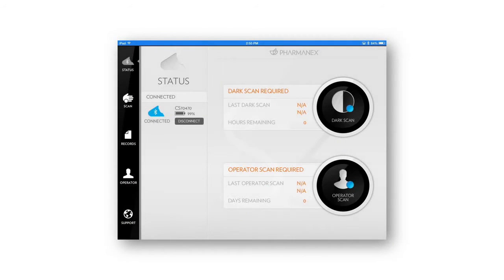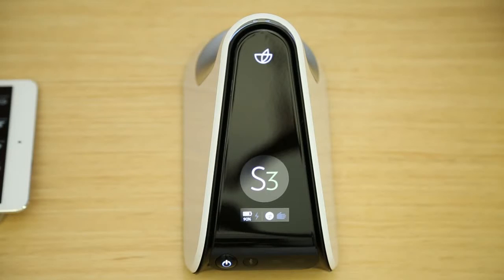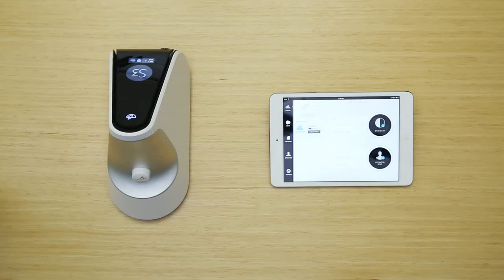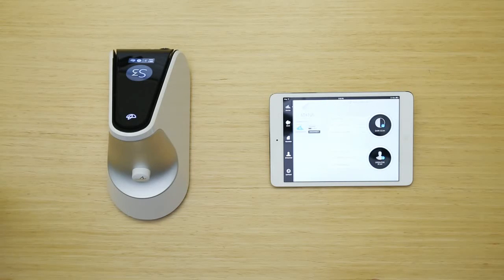When your iPad is connected to the scanner, the scanner status will display in the Status tab, and the Bluetooth button on the back of the scanner will stop blinking and remain on. Next, you'll need to perform a dark scan and an operator scan.